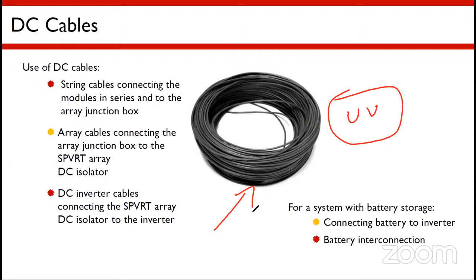DC is 1.2 times AC, so the DC cable should have 20% more current carrying capacity than an AC supply cable. That is also a very important factor, which is why DC cables are specially designed. They are also UV protected, so even in the open atmosphere they can withstand climatic conditions, give better performance, and have very low EMI interference losses. These are the main reasons why we specifically need DC cables.